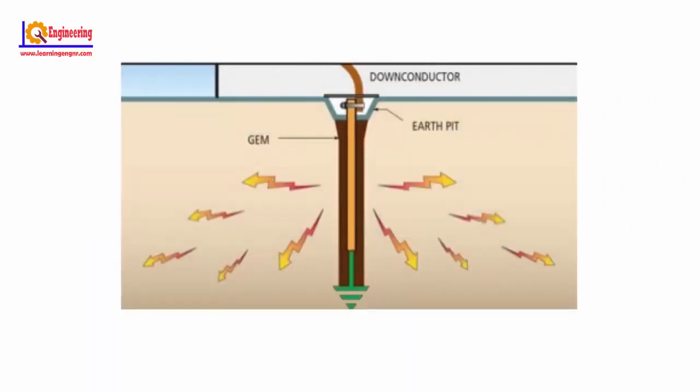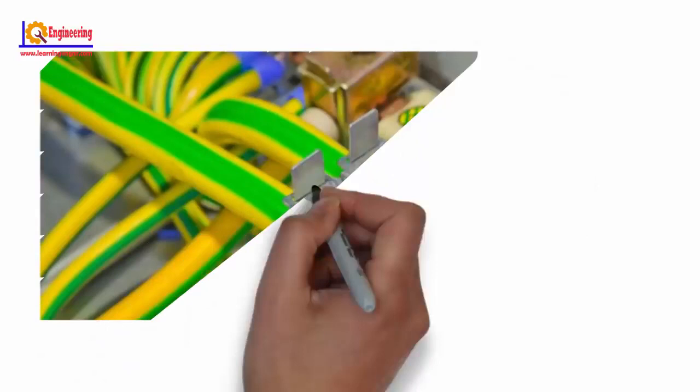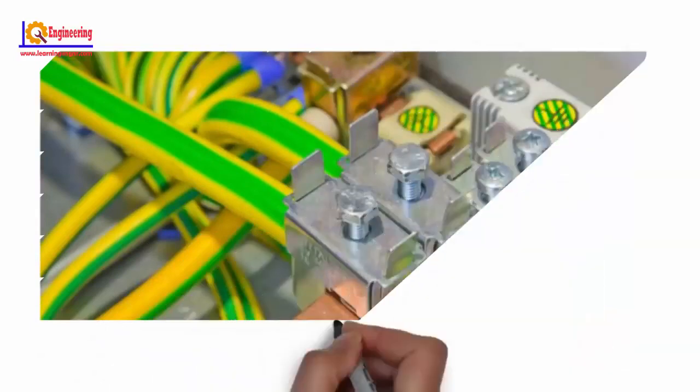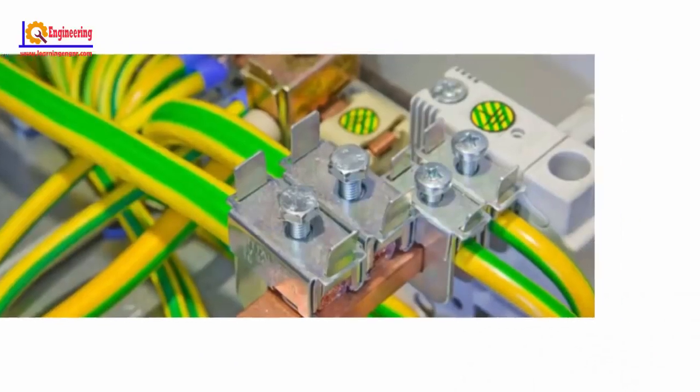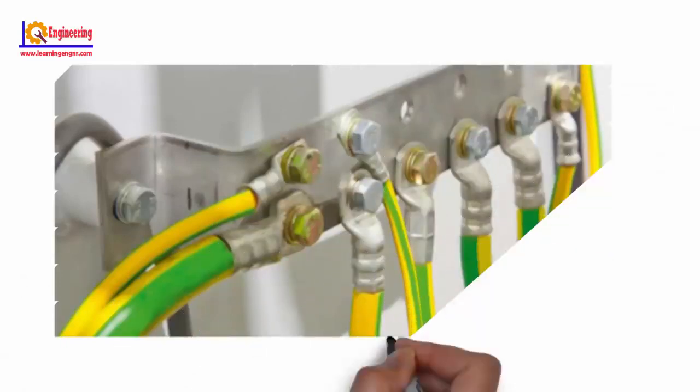The method of connecting non-current carrying parts of electrical equipment or the neutral point of the supply system to the earth through a wire having negligible resistance is called electrical earthing. Earthing protects the electrical equipment from lightning strokes and earth fault conditions. It provides the easiest path for the fault or leakage current to flow through it.